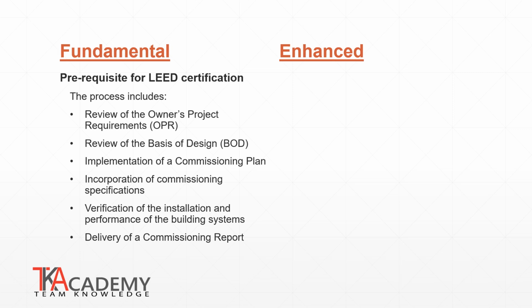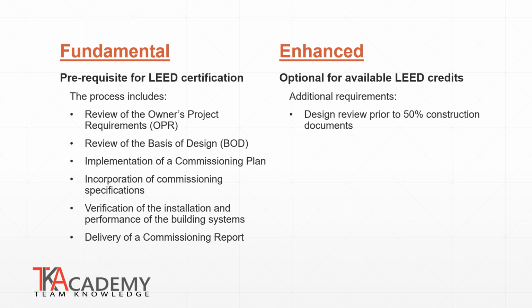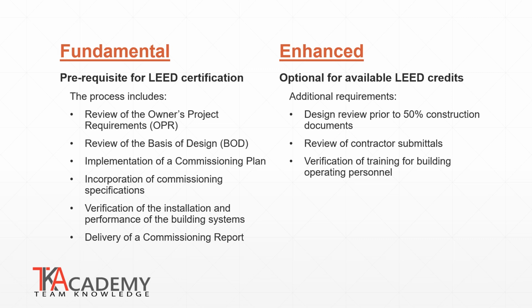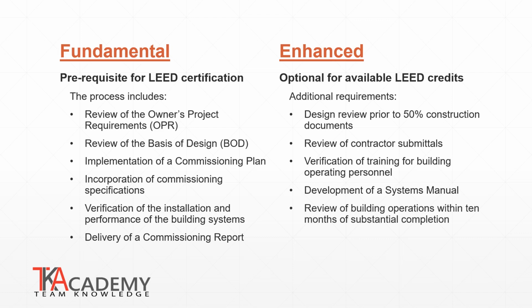Enhanced commissioning is optional, and it can be used to achieve additional LEED credits that can apply toward achieving a higher LEED certification rating. Enhanced commissioning services include all aspects of fundamental commissioning with a few additional requirements. During design, enhanced commissioning includes the requirement for the commissioning provider to review the 50% complete design documents. Enhanced commissioning also requires that the commissioning provider reviews the contractor's submittals, verifies that training has occurred for the building operational personnel, develops a systems manual, and reviews building operations within 10 months of the building completion.